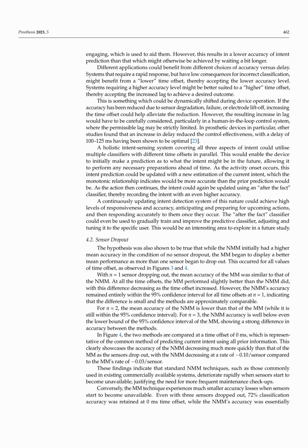This is something which could be dynamically shifted during device operation. If the accuracy has been reduced due to sensor degradation, failure, or electrode liftoff, increasing the time offset could help alleviate the reduction. However, the resulting increase in lag would have to be carefully considered, particularly in a human-in-the-loop control system where the permissible lag may be strictly limited.